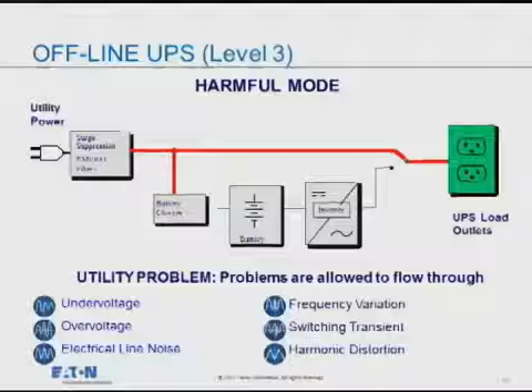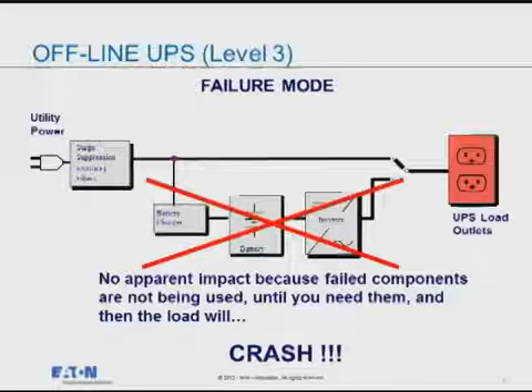Another problem is the components are offline. If they've failed, if the battery's failed, how do I know, and when do I know they've failed? When I have a power failure. When do I need those components to operate? When I have a power failure. So eventually I'm going to have a component fail and I won't know until I go to use it. And guess what? I'm going to have a failure. So it's really a reactive approach to power quality.